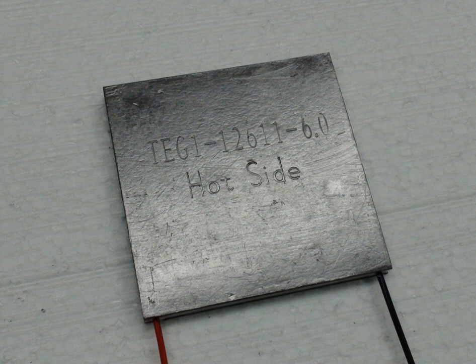Thermoelectric cooling uses the Peltier effect to create a heat flux at the junction of two different types of materials. A Peltier cooler, heater, or thermoelectric heat pump is a solid-state active heat pump which transfers heat from one side of the device to the other, with consumption of electrical energy, depending on the direction of the current. Such an instrument is also called a Peltier device, Peltier heat pump, solid-state refrigerator, or thermoelectric cooler (TEC). It can be used either for heating or for cooling, although in practice the main application is cooling.